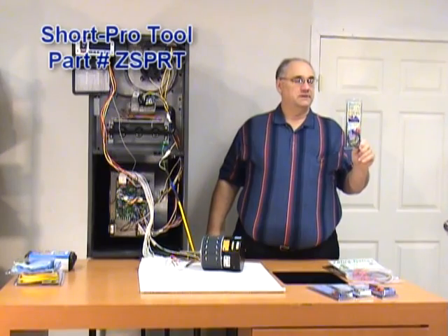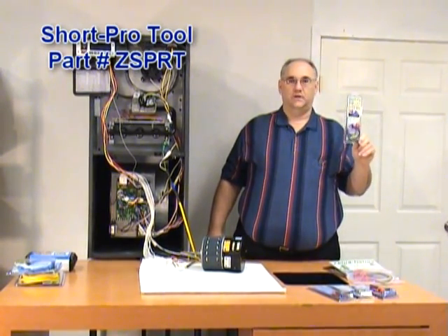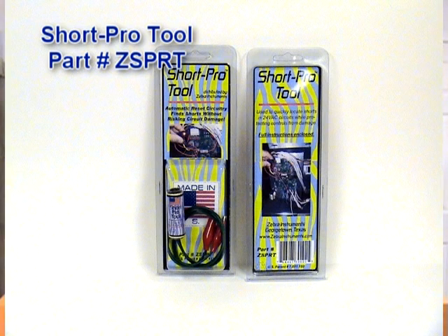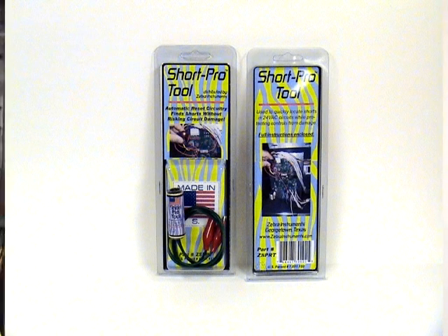Our newest product at Zebra Instruments at mid-2007 is called the Short Pro tool. It was invented by a technician in San Antonio. We saw his efforts at making the tool and we really liked it. This is an inexpensive tool that makes it fast to find shorts in air conditioning systems without blowing a pocket full of fuses. I mean, how many times have you been tempted to put a jumper wire over a fuse on Mrs. Cartwright's board so that you didn't blow fuse after fuse while you were looking for wherever that line was shorted? You know, maybe the dogs chewed through it on the outside, or maybe the contactors or gas valve shorted. This is a way to do that safely.